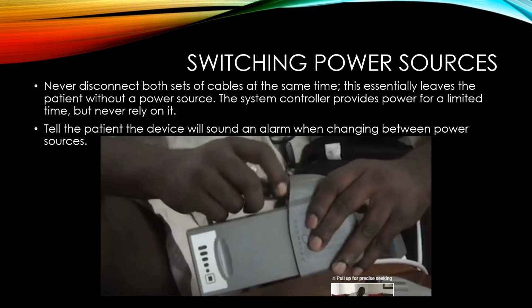Never disconnect both sets of cables at the same time. This essentially leaves the patient without a power source. The system controller itself provides power for a limited amount of time, but never rely on it. Tell the patient the device will sound an alarm when changing between power sources, and it is very loud.